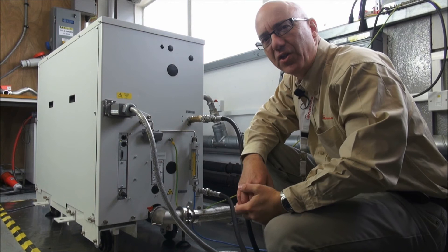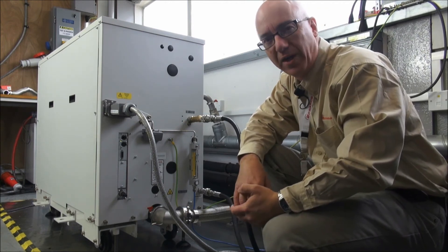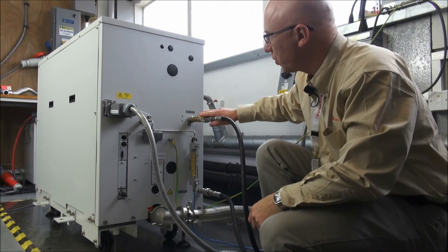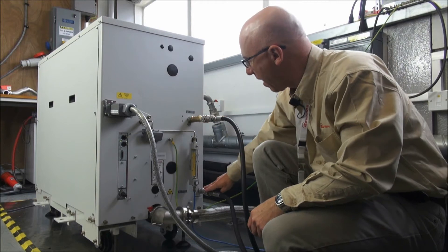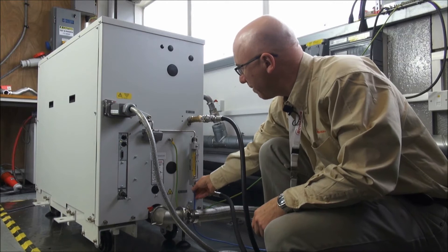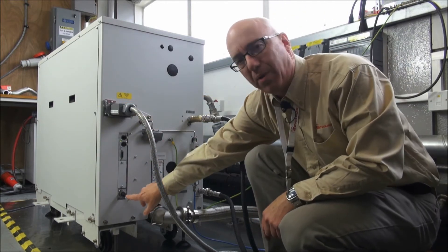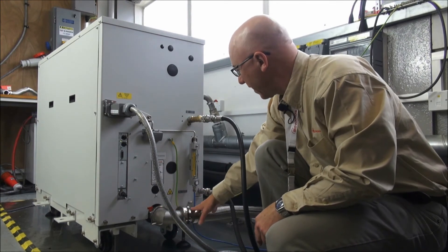So now we've got our GXS installed and in place. The process connection, the fore-line, is securely connected to our process. The isolation valve is closed, so we'll just check around the back of the pump. We have water inlet connected through the recommended strainer, the purge gas correctly fitted to the flow meter, the power securely connected through the Harting connector, the all-important EMS plug firmly in place, and the exhaust securely connected in.